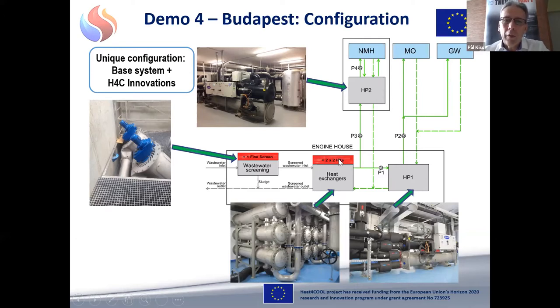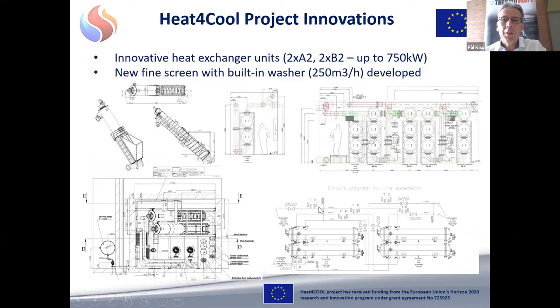Where we worked a lot is to develop a good wastewater screening and a very good heat exchange. So we developed our equipment in this respect. The invention that we made here is basically for the screening, a washing system for good maintenance. So we installed automatic washing of the system, which lets us do the maintenance very easily and not need to be on site. Then we worked on the further development of the heat exchangers, where we invented special inlet chambers and special elements of the heat exchange to do easy maintenance and easy flow.